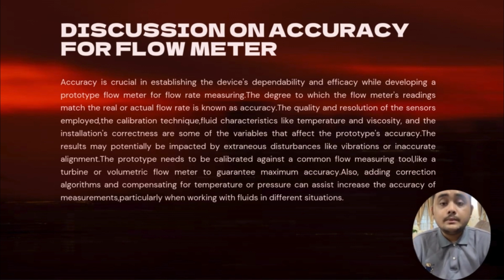So accuracy is a fundamental performance criterion when selecting and using a flow meter. It refers to how closely the flow meter's reading matches the actual flow rate of a fluid, for example liquid, gas or steam. The more accurate a flow meter is, the smaller the difference between the measured and the true flow. So flow meter accuracy is usually expressed as a percentage of the actual reading, full scale or calibrated span. For instance, an accuracy of plus minus 1% of reading means the measurement can be 1% higher or lower than the true flow.